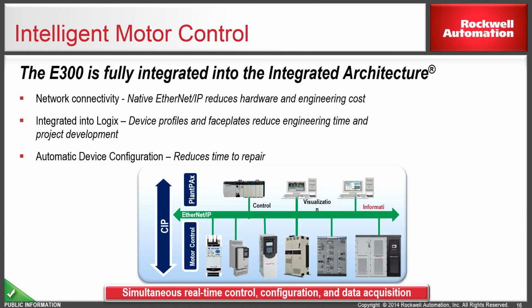So network connectivity is one, which has native Ethernet IP, which reduces your hardware engineering cost, and direct integration to the Logix platform. There are profile plates available, and there are add-on profiles which directly import, and you can configure the devices in a single software. Automatic device configuration significantly helps you to reduce time to repair. If any fault occurs in the device, you don't have to reconfigure the device. You just remove it from the network and place the new device, and it automatically configures. It significantly helps you with re-engineering the device.